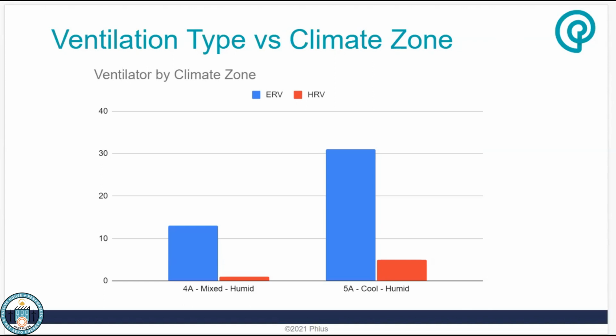That's not to say HRVs are worse by any means. They just don't have that humidity recovery. But what heat recovery ventilators lack in that humidity retention, they typically make up for in having higher recovery efficiency for the heating. So they actually recover a greater percentage of that exhaust heat that's leaving the building. So, typically an HRV can have anywhere from like a 90 to 95% recovery efficiency, whereas ERVs, for heating at least, have a recovery efficiency anywhere between 75 to maybe 85 on the high end for heat recovery. So that's kind of the trade-off you have to make on these projects.